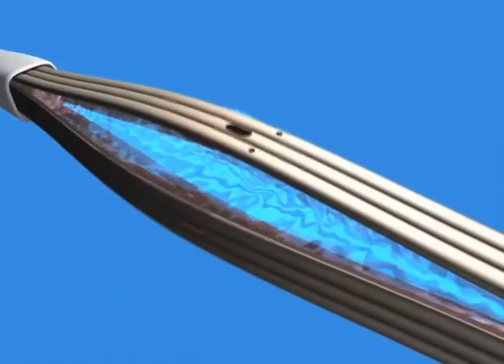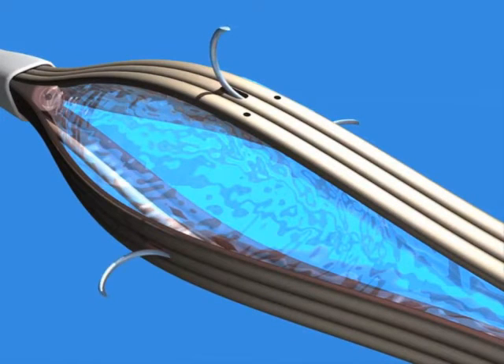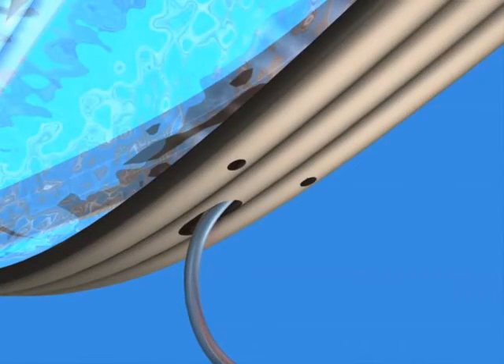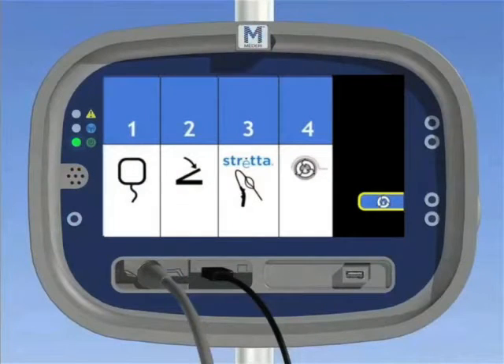11. Inflate the Stretta catheter balloon with 25 ml of air through the PRV. Extend and retract the needles, then inspect needles for full extension and retraction. 12. Push the prime button on the lower right of the generator to initiate priming of the Stretta catheter. Inspect irrigation exit ports and ensure water flows through the device near the base of each needle. Push the prime button again to stop the prime cycle.